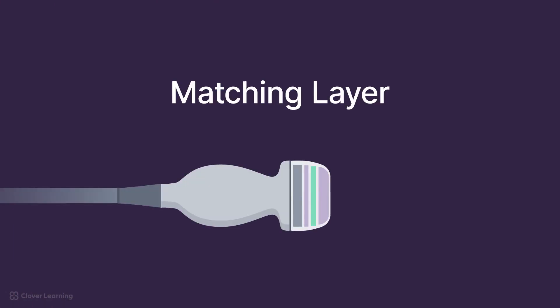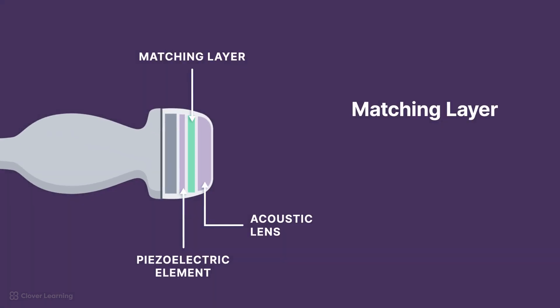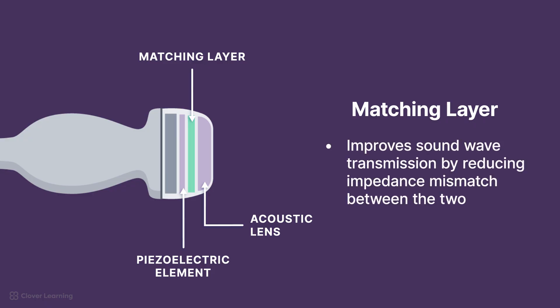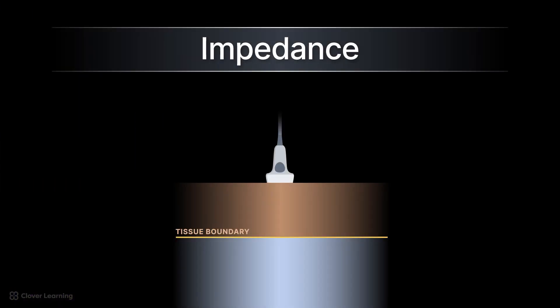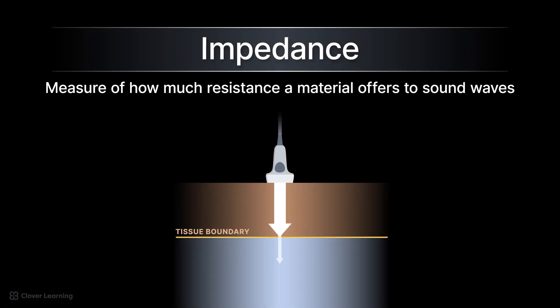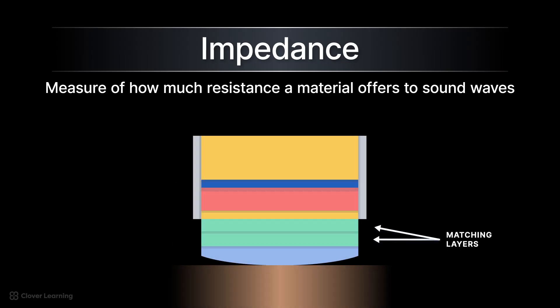The next component, moving toward the front of the transducer, is the matching layer. This layer sits between the crystal and the acoustic lens, improving sound wave transmission by reducing the impedance mismatch between the two. Impedance is a measure of how much resistance a material offers to sound waves. If there is a large difference in impedance between two materials, most of the energy created is reflected back rather than transmitted. Matching layers are designed to have an acoustic impedance value between that of the crystal and the tissue, so it can act as a bridge to gradually transition the impedance between the piezoelectric crystal and the patient.